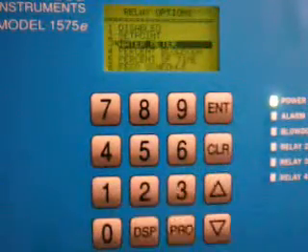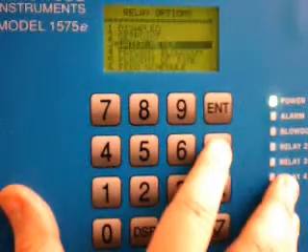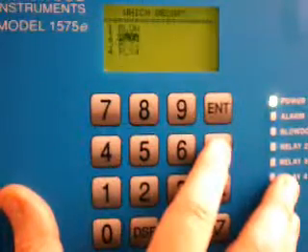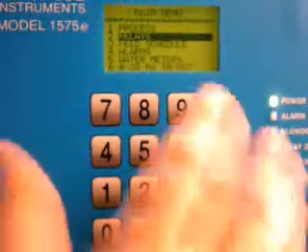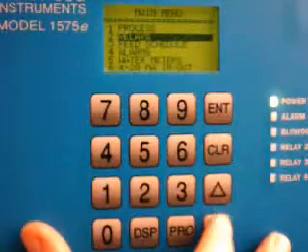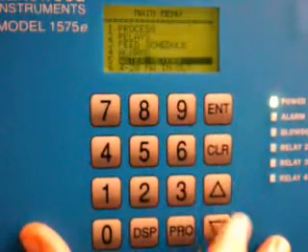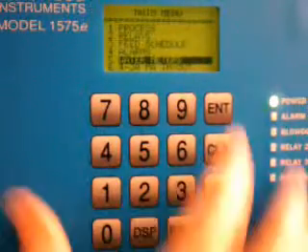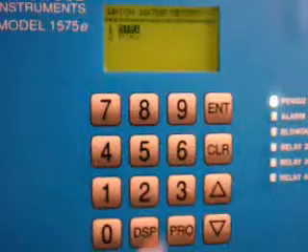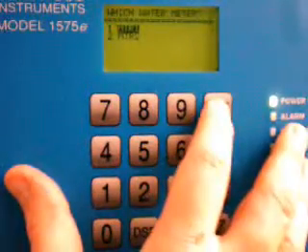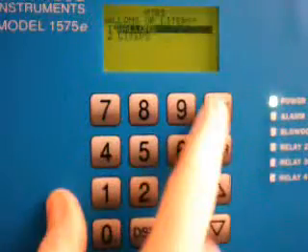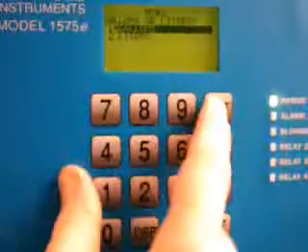Well, I'm not done yet because the controller knows that you're the human being and you're in charge. So I have to clear out to the main menu and actually drop down to water meters. I have to tell it what sort of water meter is installed on the terminals for meter 1. So I go to meter 1, and again, I can press 1 or I can just hit enter. It's going to be in gallons.